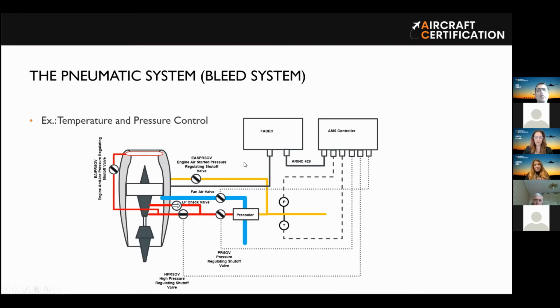Here is a schematic of the pressure and temperature control. So as I told you, the temperature control function is done by the fan air valve and precooler. And the pressure control function is performed by the pressure regulating shut-off valve here. So the AMS controller reads the pressure and temperature in the manifold and provides commands for these valves. By modulating the fan air valve, you can control temperature, and by modulating the pressure regulating valve, you can control the pressure.